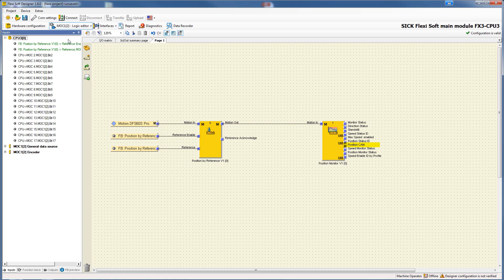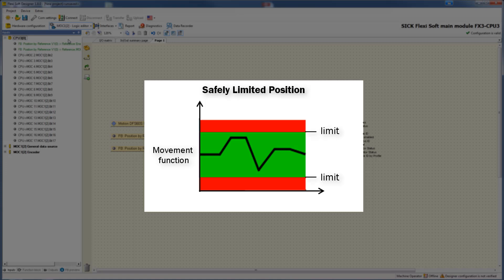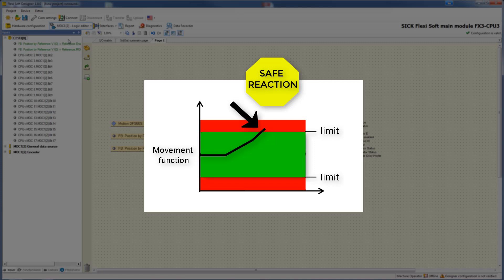Position cam can be configured for each position range for implementing electronic cams. Looking at the graphic explaining the safety function safely limited position: the valid position range in which the drive is allowed to move is painted in green, while the invalid position range outside the limits is shown in red. The MOC1 safely monitors the movement of the drive. If the permitted range is exceeded — meaning the drive moves into the red area — a safe reaction is generated.